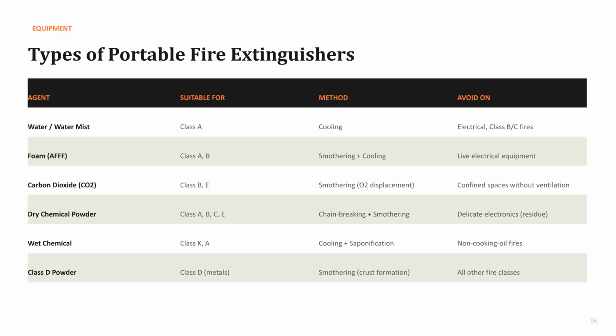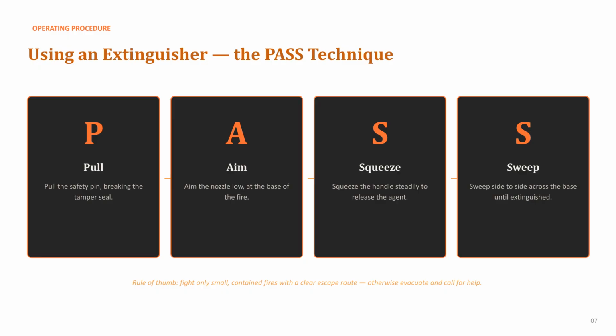Let's cover portable fire extinguishers and their proper applications. Water cools Class A fires, but avoid using it on electrical or Class B and C hazards. Foam smothers Class A and B fires, but never live electrical equipment. Carbon dioxide smothers Class B and E fires by displacing oxygen, though unventilated confined spaces should be avoided. Versatile dry chemical powder interrupts chain reactions across Class A, B, C, and E, but leaves residue on delicate electronics. Finally, wet chemicals cool and saponify Class K cooking fires, while specialized Class D powder smothers metal fires through crust formation.